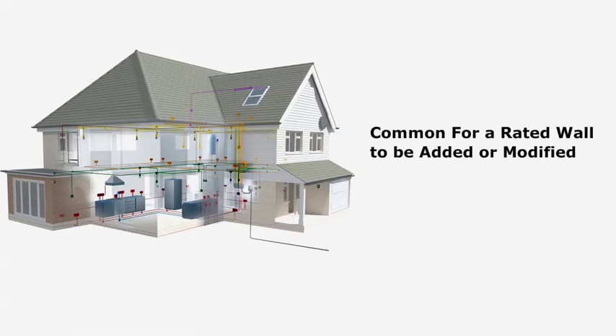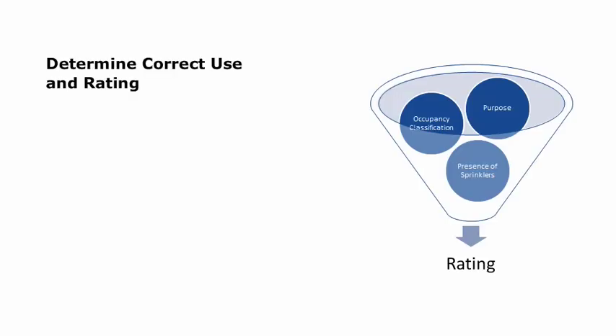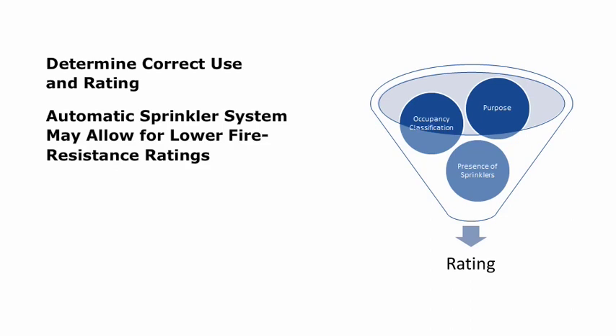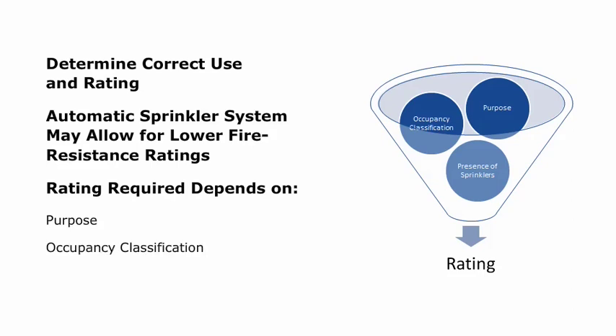It is very common for a rated wall to be added or modified during an interior project, whether it includes a new layout, new finishes, or the addition of wiring and cabling. Work done may affect a rated wall, so it is important to determine the correct use and rating of the fire barrier, horizontal assembly, or fire partition when adding a new one or modifying an existing one. For all three types, the presence of an automatic sprinkler system may allow for lower fire resistance ratings. The rating depends on the purpose of the assembly, the occupancy classification, and whether the space has sprinklers that meet current code requirements.